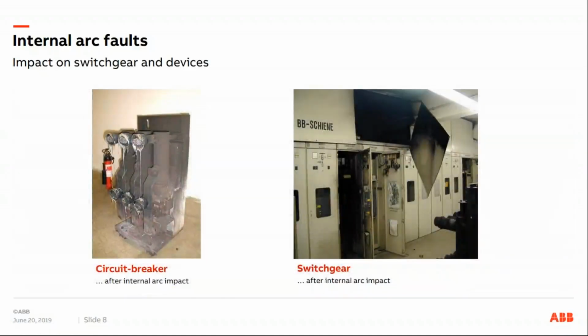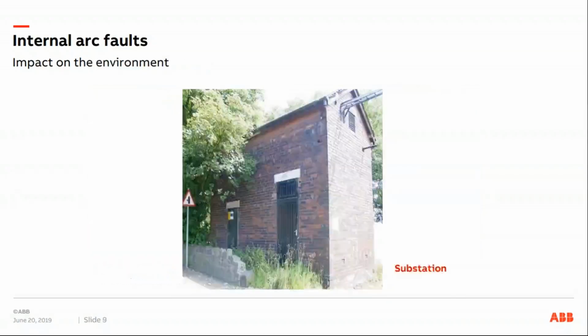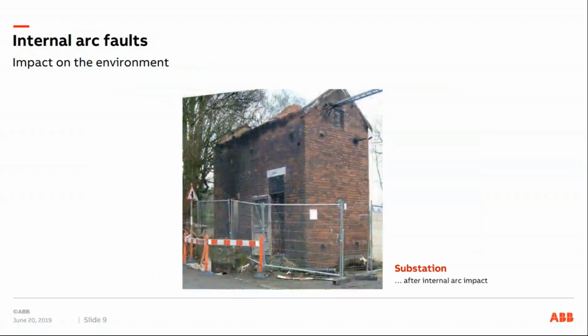So here we can see some pictures showing the effects or the impact on the circuit breaker, completely melted and destroyed, and the switchgear after an internal arc impact. Here we can see a substation before an arc fault and the leftovers after an arc fault.